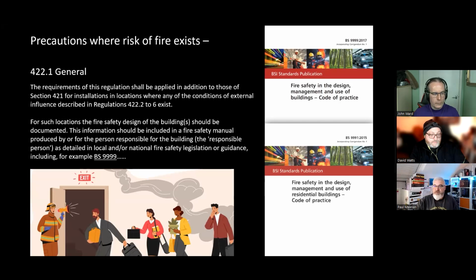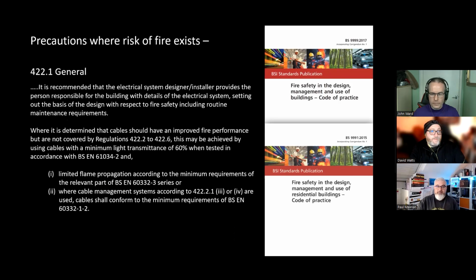Now, that's great to know, but we need to know how we contribute towards that. So it is recommended that the electrical system designer installer, who may not be a fire engineering expert, provides the person responsible for the building with details of the electrical system, which he should be considering all the fire safety requirements in 7671, setting out the basis of design with respects to fire safety, premature collapse, compartmentation, fire resistant cables, life safety services, which then leads you to BS 8519, which is a brilliant document, including routine maintenance. Again, more mainly commercial, industrial, or places where there's a client owning the building.